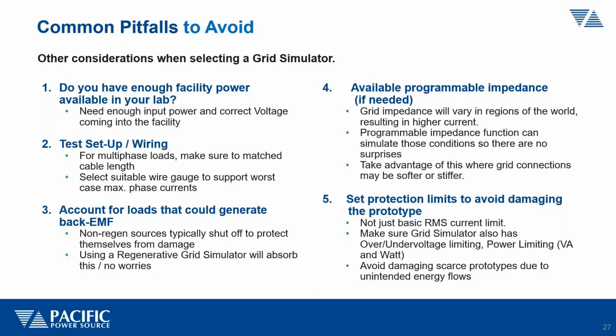Keep those short. Also consider whether you're able to handle loads that kick back energy, such as motors, motor drives, and other equipment that doesn't just absorb power but occasionally returns power. Having a regenerative grid simulator allows you to do that - it'll absorb that energy and put it back on the grid. So it's not only energy efficient and green, but also capable of handling loads that a non-regenerative grid simulator wouldn't be able to handle; they would protect themselves and shut off in those situations. So make sure that if you have those kinds of loads, your grid simulator is regenerative.